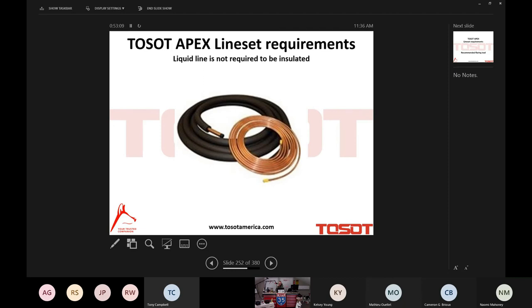Liquid line, not required to be insulated. So in retrofit situations where we're just changing the outdoor unit, no need to insulate an uninsulated liquid line. It's a beautiful thing.